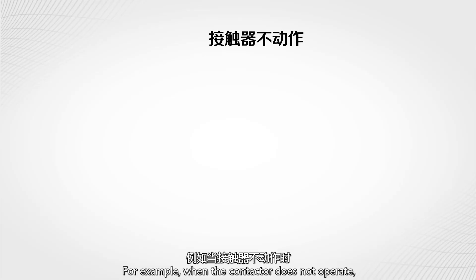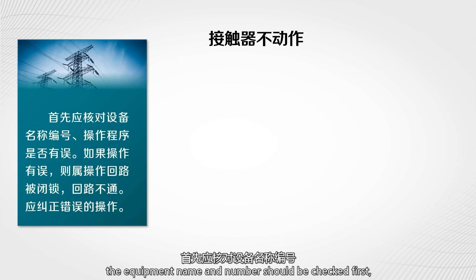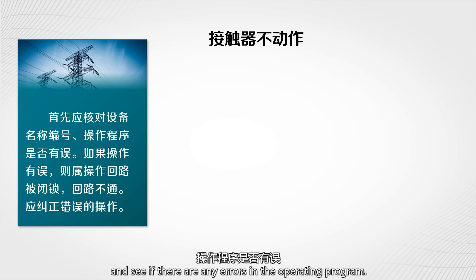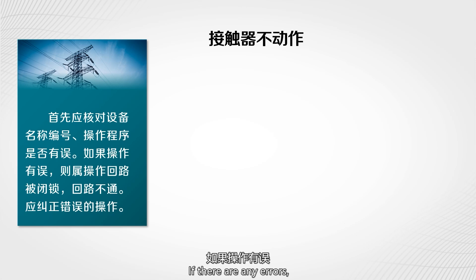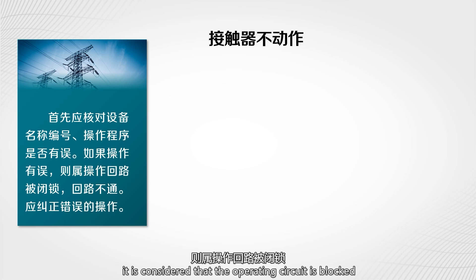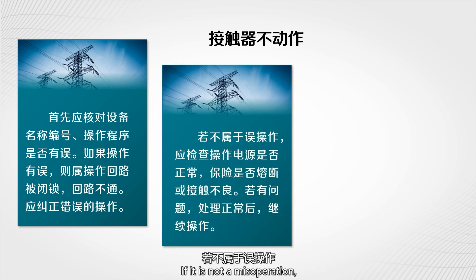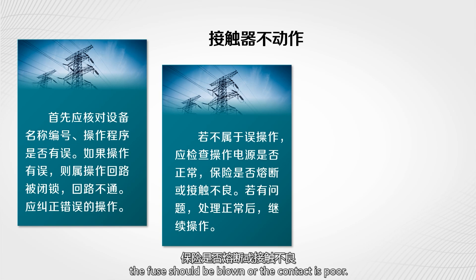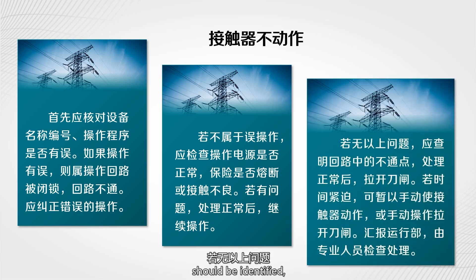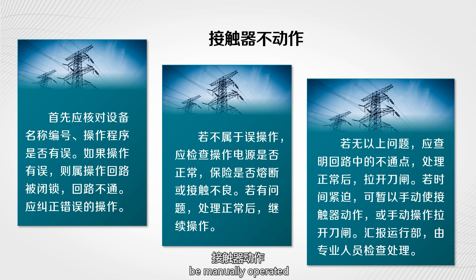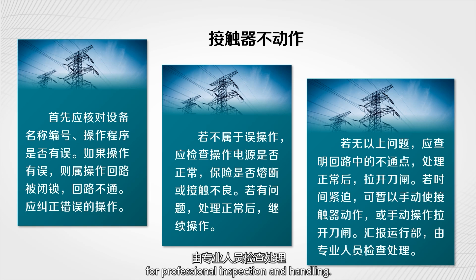For example, when the contactor does not operate, check the equipment name and numbers first to see if there are any errors in the operating program. If there are errors, it is considered that the operating circuit is blocked and the circuit is not connected — correct the incorrect operation. If it is not a mis-operation, check the operating power supply for normalcy, check for blown fuses or poor contact. If no problems are found, identify the disconnection point in the circuit and open the knife switch after normal handling. If time is tight, the contactor can be manually operated or the knife switch manually opened, and the operation department should be reported for professional inspection.